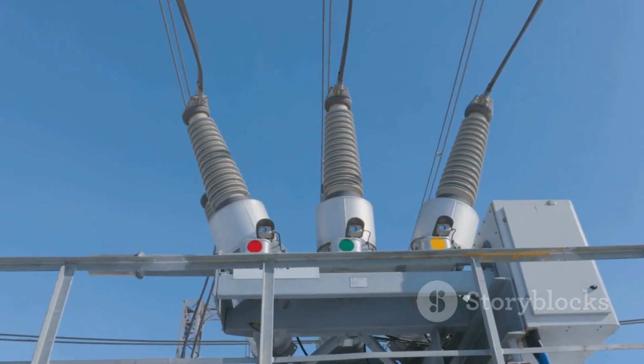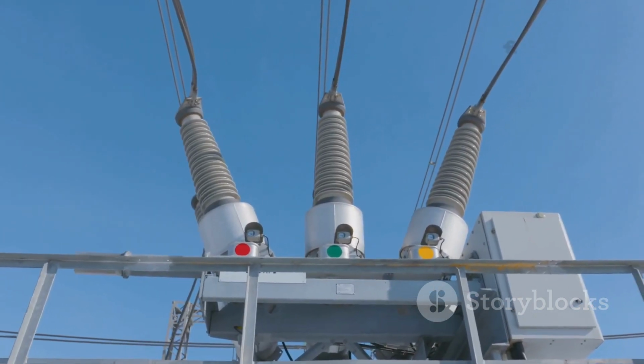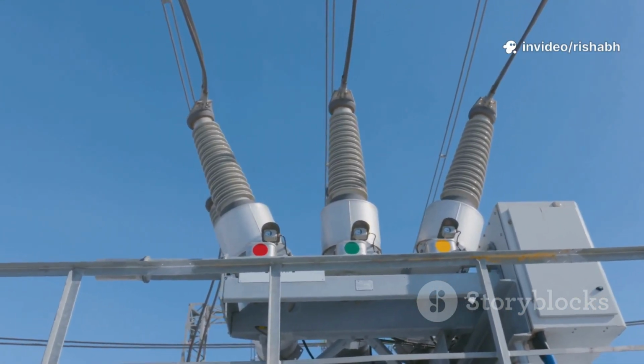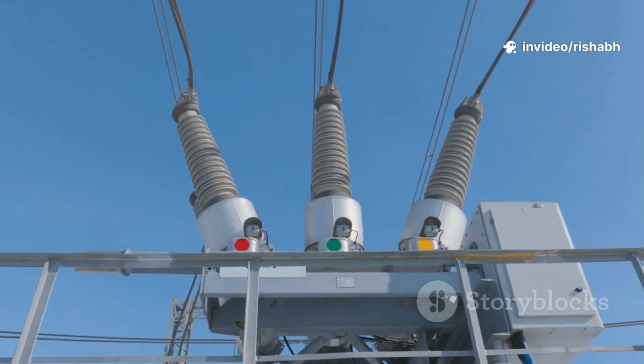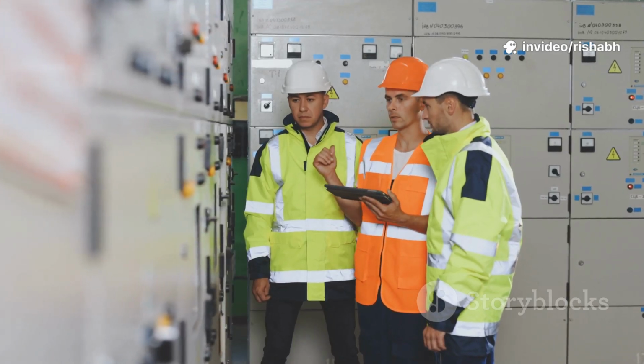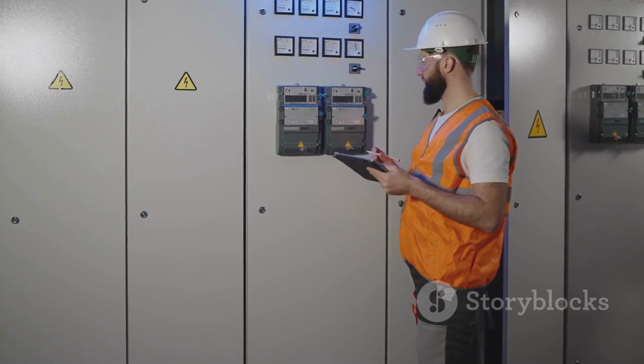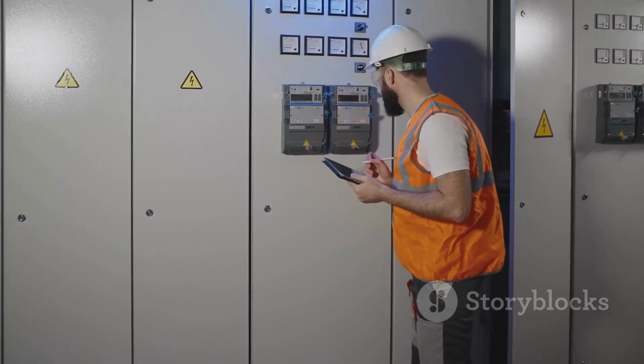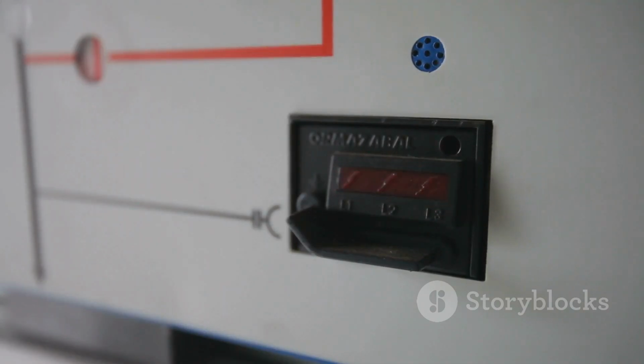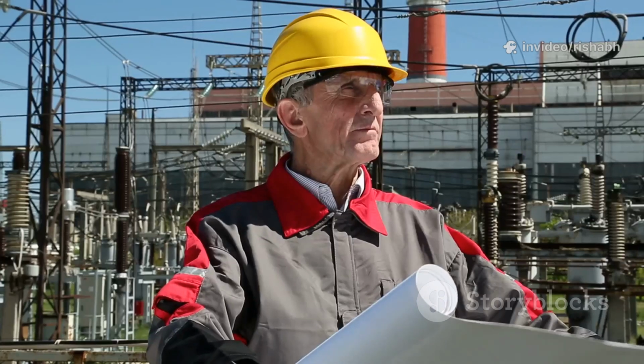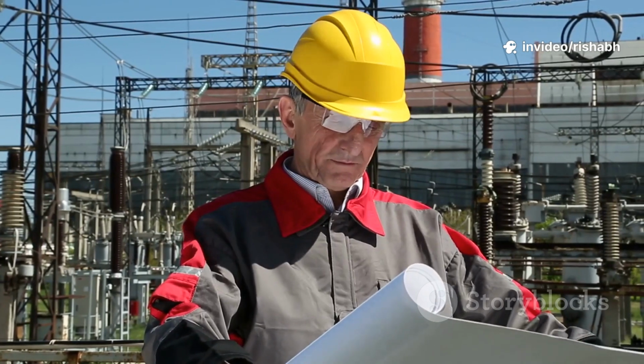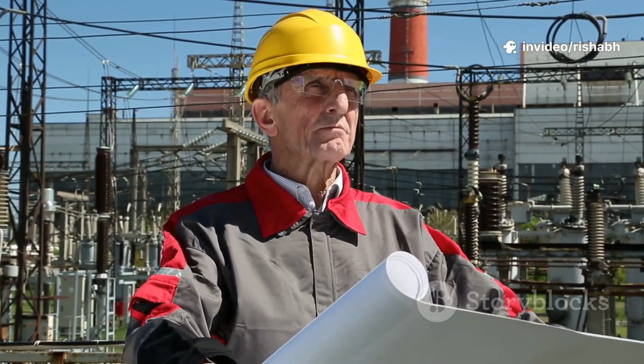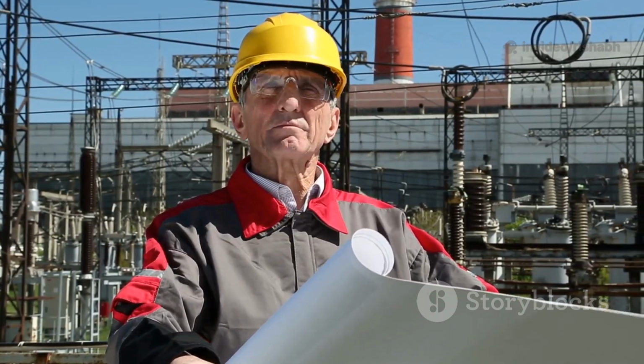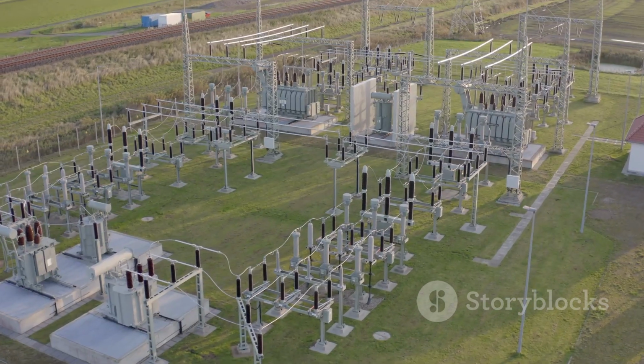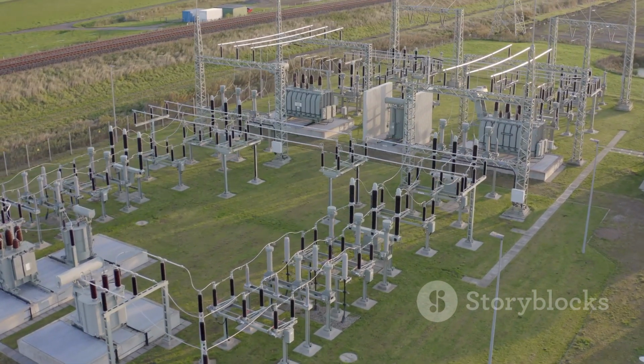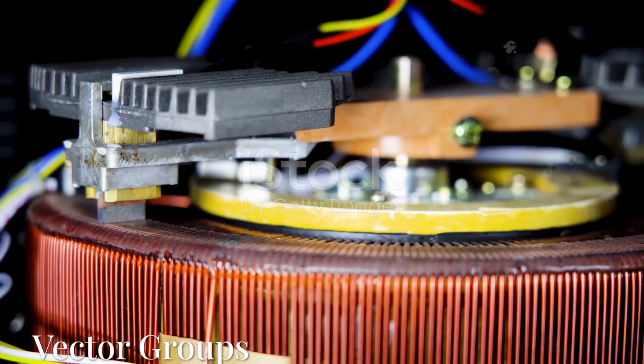It's a shorthand notation that describes the winding configuration and the phase relationship between the high voltage and low voltage sides. Think of it as a compatibility label. Before connecting two transformers, engineers must check this label. If the vector groups don't match, they simply cannot be connected. Understanding this concept is not just academic. It is a crucial piece of practical knowledge for anyone working with electrical power systems. It's what separates a stable, functioning grid from a chaotic and dangerous one.